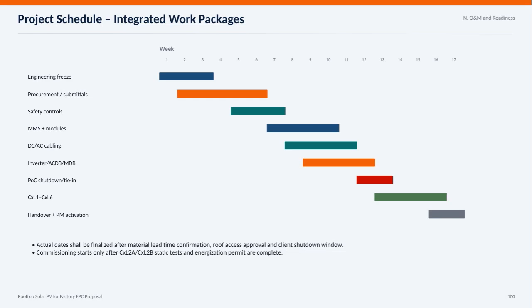Here we have the integrated project schedule for the rooftop solar PV installation at the factory. The timeline is spread across 17 weeks, covering all key work packages from engineering freeze to handover and project management activation. It's important to note the sequence of activities here, starting with engineering freeze, then moving into procurement and submittals, followed by safety controls and equipment installation including MMS and modules, DC/AC cabling, and inverter setups. Commissioning activities labeled as CXL1 through CXL6 are scheduled toward the end, with a critical pause for point of connection shutdown and tie-in to ensure safety and system integrity.